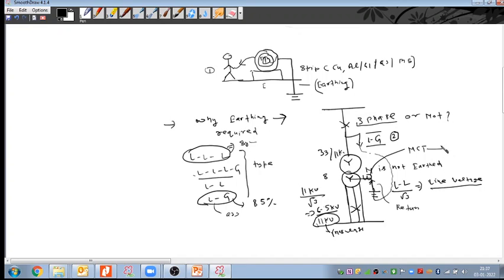This NCT will sense the current. It will give output to one earth fault relay. In the switchyard we use the REF relay, the restrictive earth fault relay, and the REF relay will sense and give a tripping command to the associated breaker. Right? This is how, if we do the earthing, we can do the protection of this equipment.